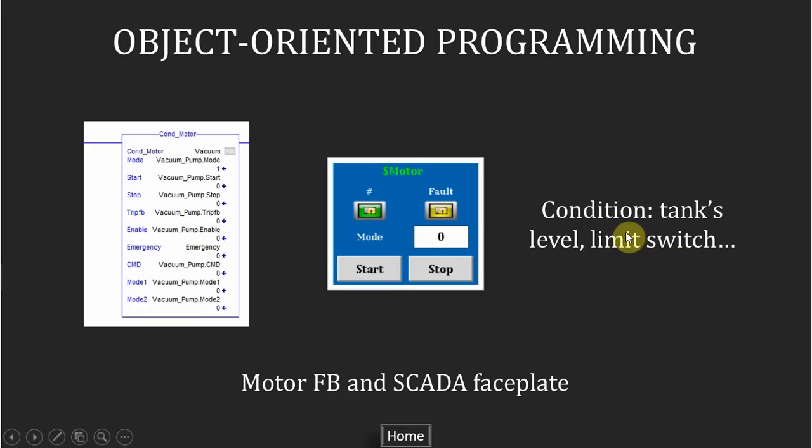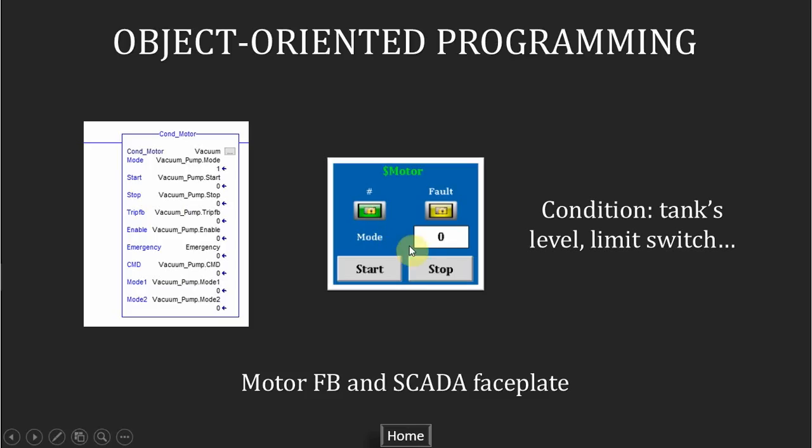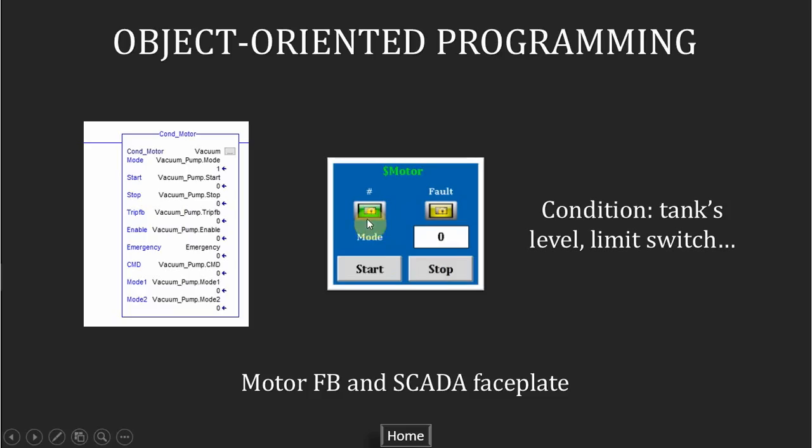For example, if the filling tank is in the high level, the bottle conveyor will run. When the sensor detects that there is a bottle at the filling position, then the conveyor stops. And this is the SCADA faceplate to control or monitor the device. Here is the numeric input that the operator can change the operating mode of the device. Mode 1 is for the automatic mode and mode 2 is manual which operator can start and stop the device immediately. This line I used to indicate the device is running or stopping or being tripped.